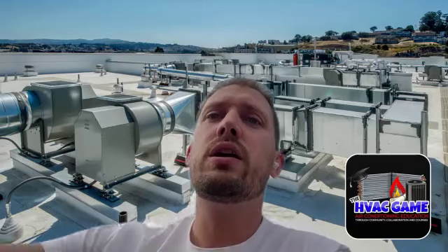And then to go on to subcool, it's basically the opposite. Subcool is when you have your refrigerant as a saturated refrigerant, vapor and liquid. Now you're in the condenser, you're removing heat, and you have your condenser fan removing the heat from the vapor refrigerant. It turns into a liquid more and more, and at some point you have 100% liquid refrigerant, but you're not fully out of the condenser yet. Whatever amount of temperature you're cooling the liquid down past the point where it's 100% liquid is your subcool, and that would be measured coming out of the condenser.